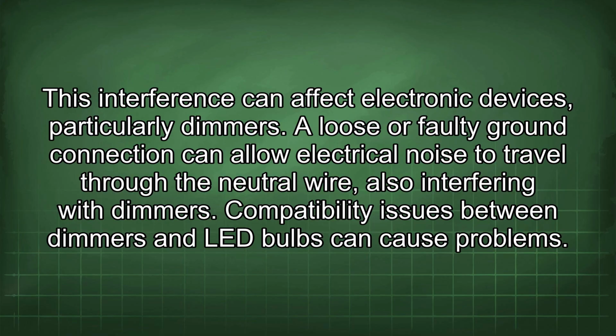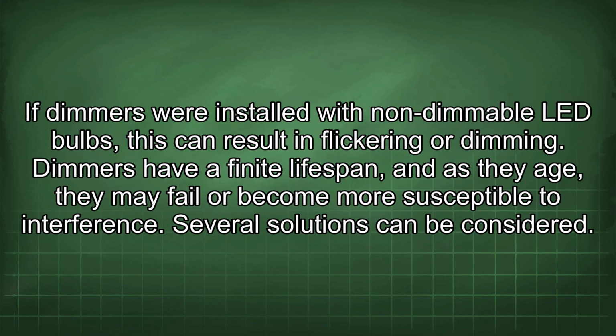A loose or faulty ground connection can allow electrical noise to travel through the neutral wire, also interfering with dimmers. Compatibility issues between dimmers and LED bulbs can cause problems. If dimmers were installed with non-dimmable LED bulbs, this can result in flickering or dimming. Dimmers have a finite lifespan, and as they age, they may fail or become more susceptible to interference.